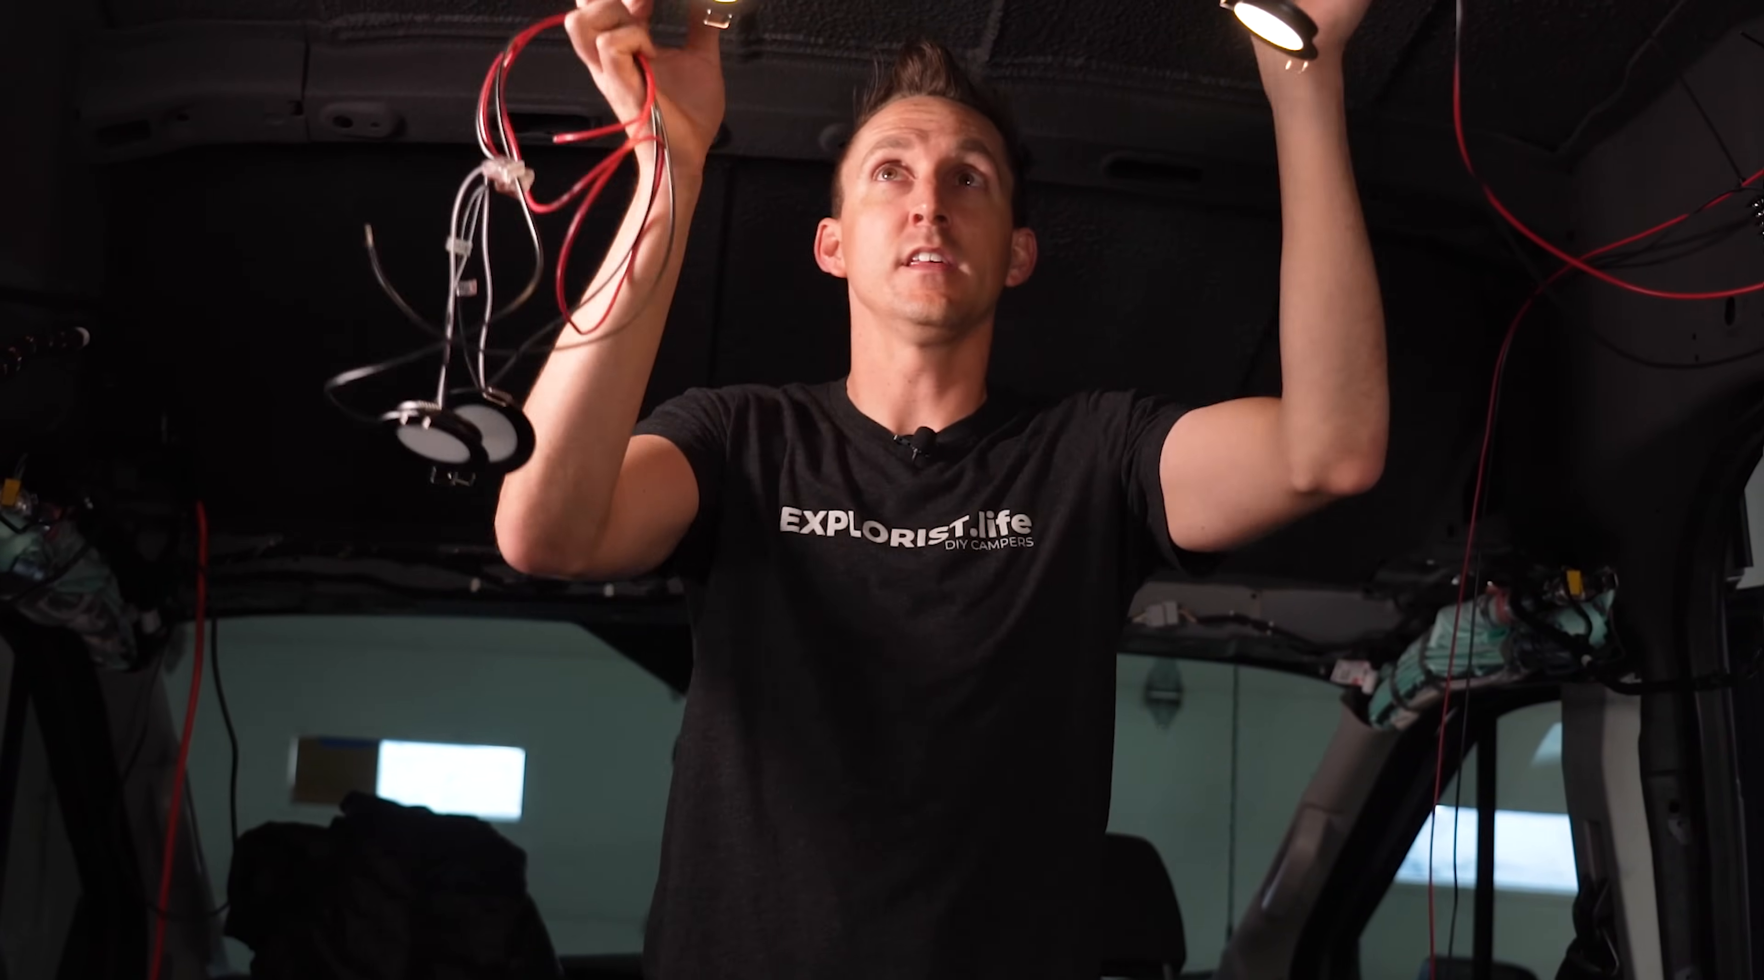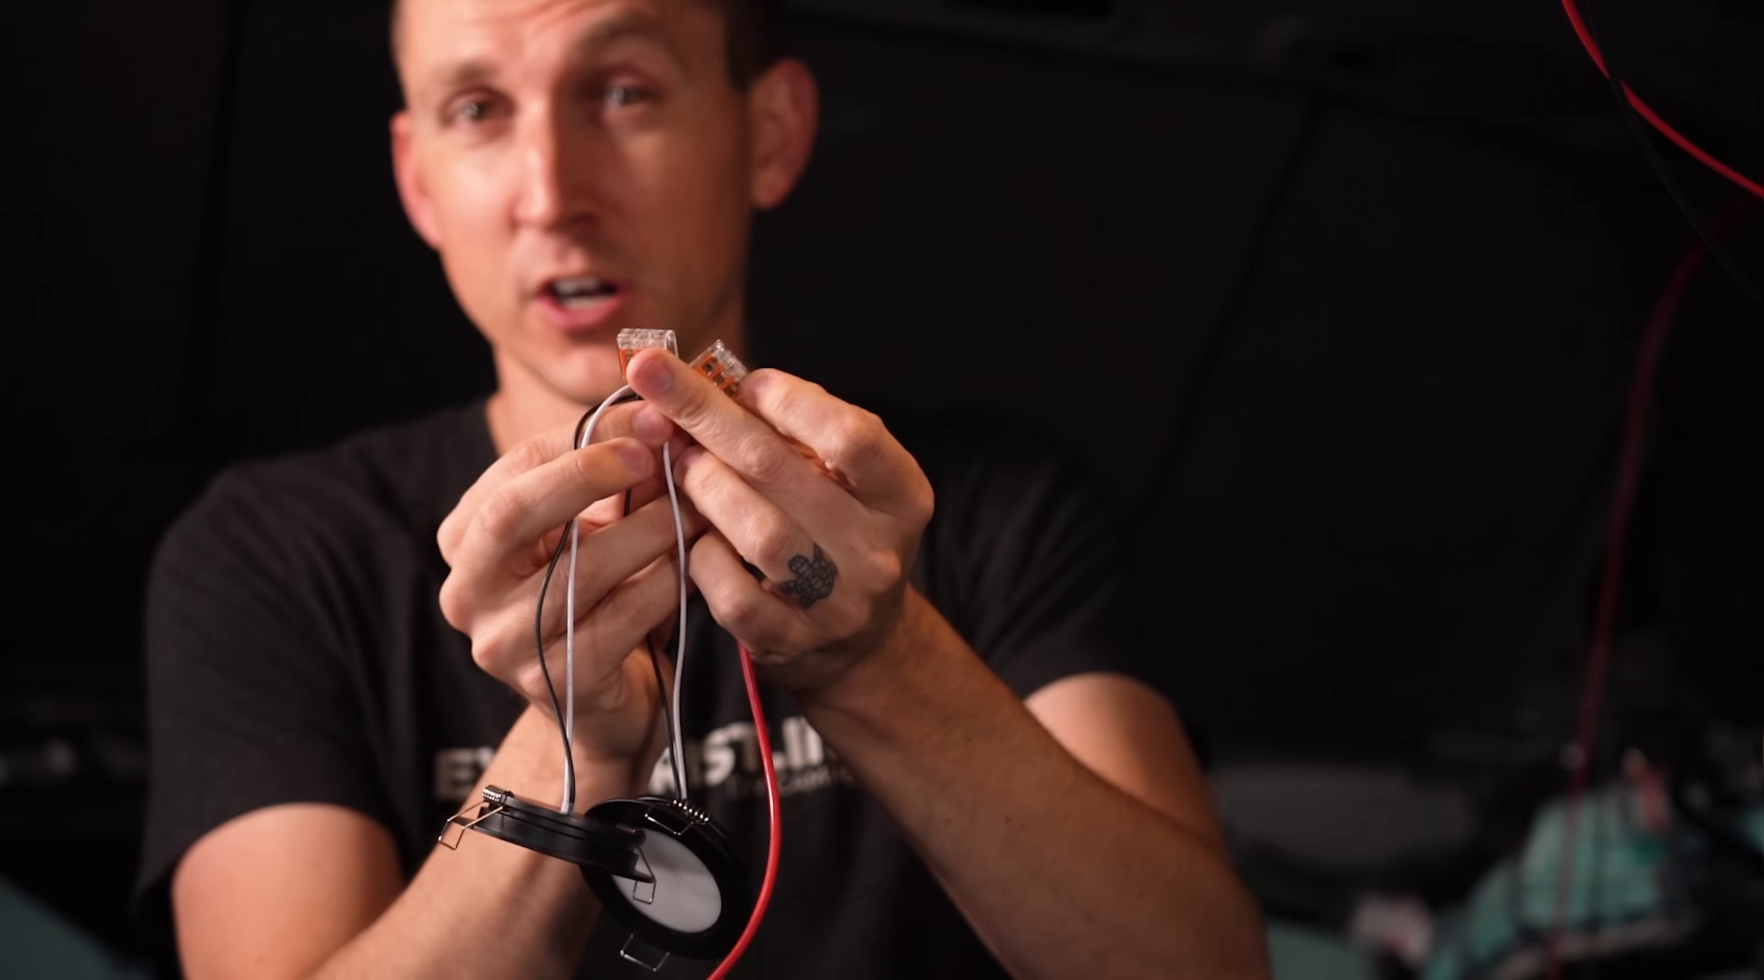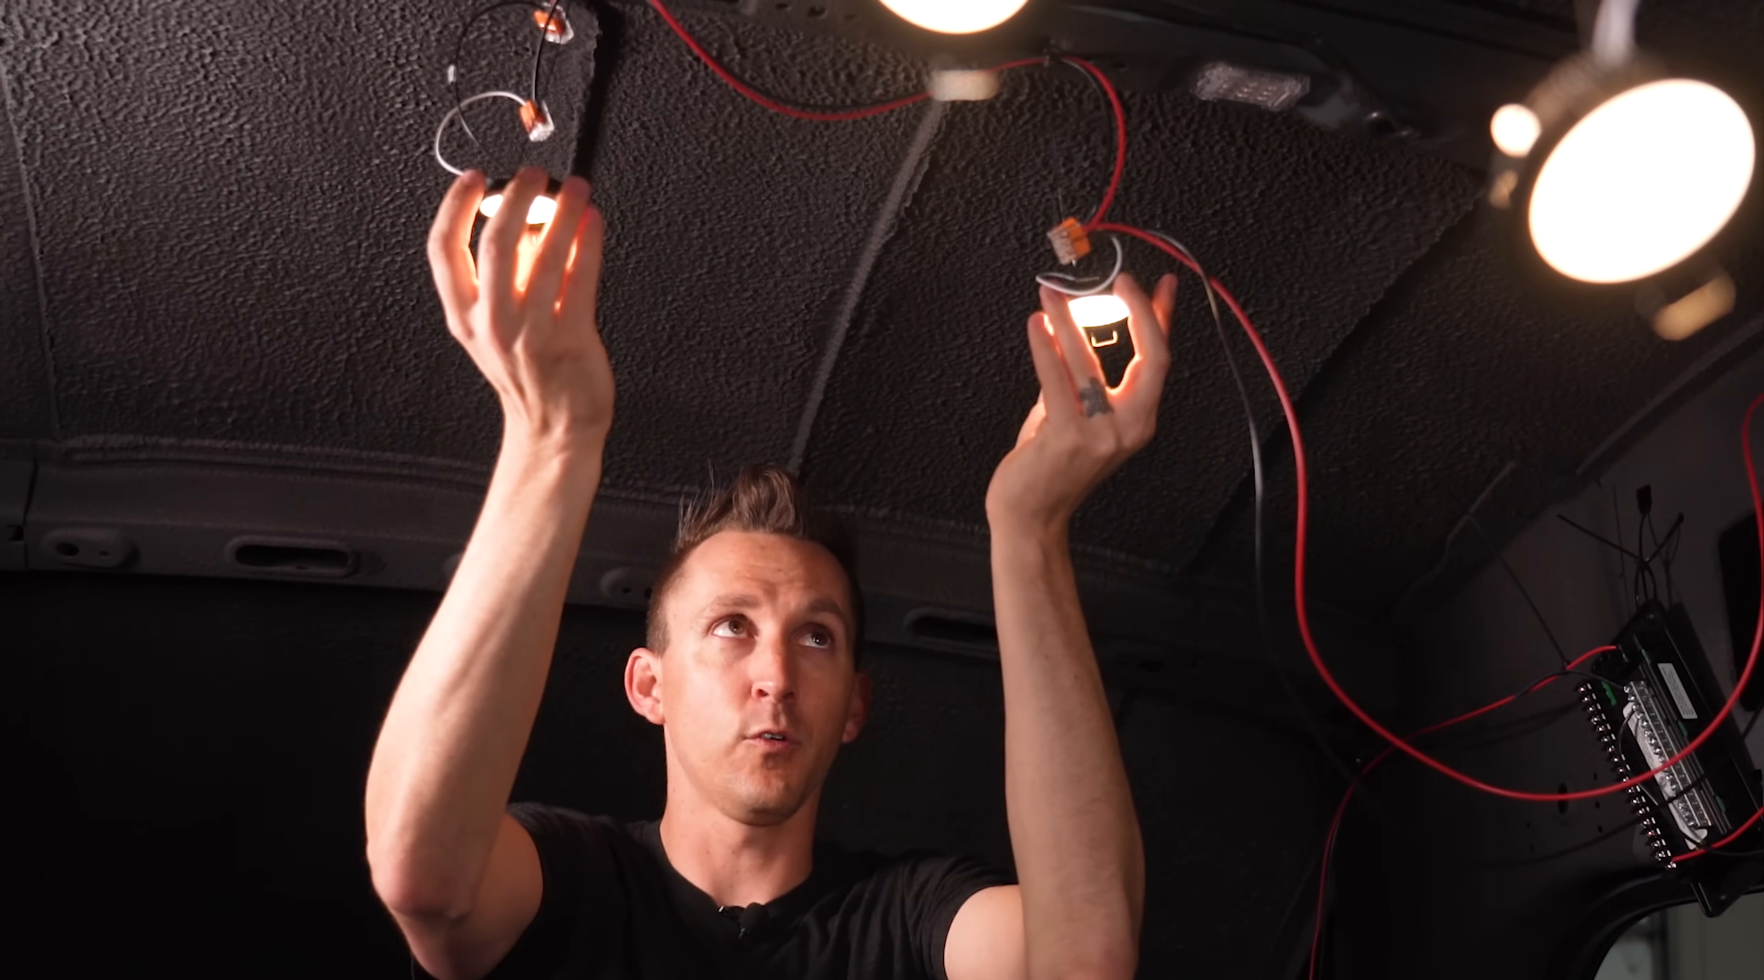The last thing is the way we wired these lights that are going to be in parallel, just all the way down. And we put lever nuts on each light just to make it easier on ourselves, because if we had done it the other way like this, if we connected both of the lights to the same lever nuts here, then this would have been up inside of the ceiling and would have been pretty hard to get to to actually make the physical connections.